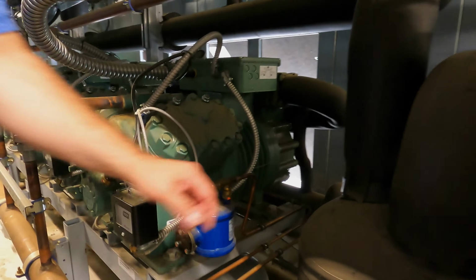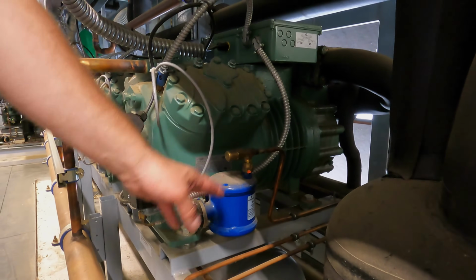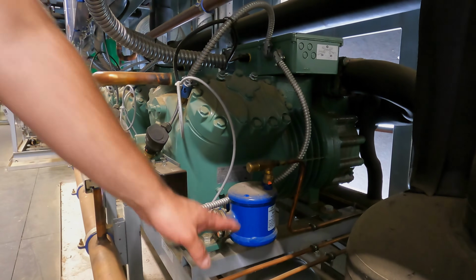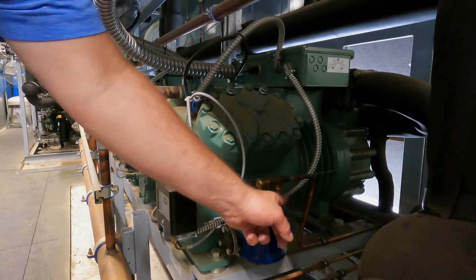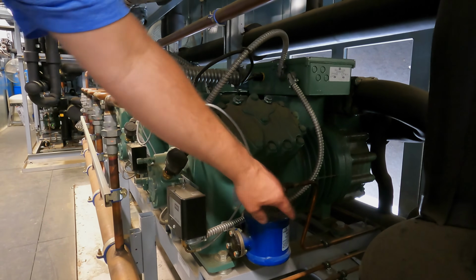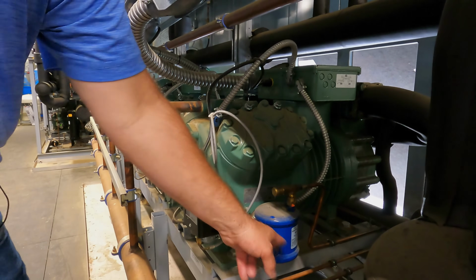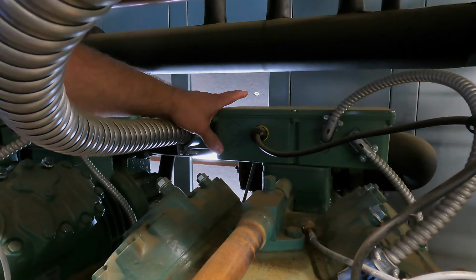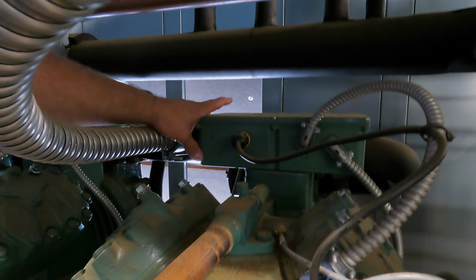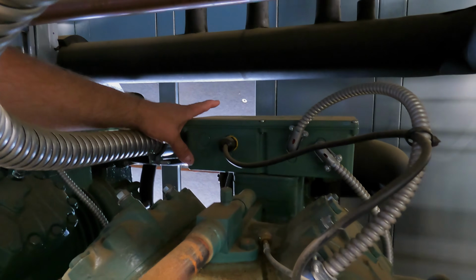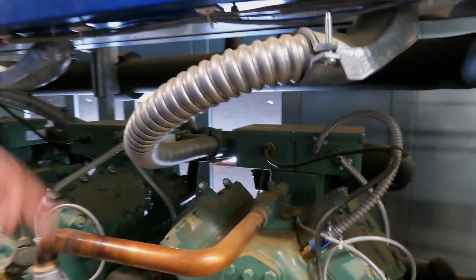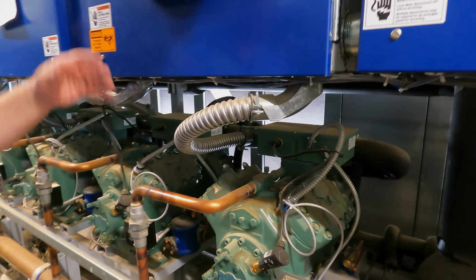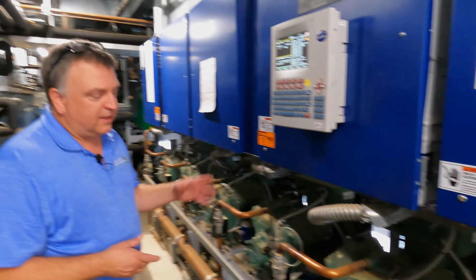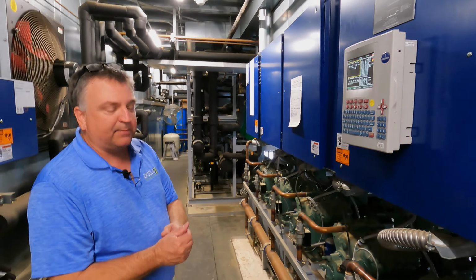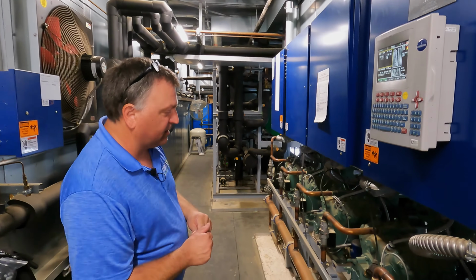This is our oil pot, oil regulator as some call it. It's basically a float system, so as oil drains out of the compressor, that float's going to open up a port and allow pressure. As long as I have the correct pressure here, it'll put more oil back into our oil pot. This is just the electrical cover for the compressor. That's where all of our safeties are. Inside there, I'm not going to take it apart, but we do have a current relay that senses if that thing's pulling the right amount of amps, and it'll shut off if it overheats.